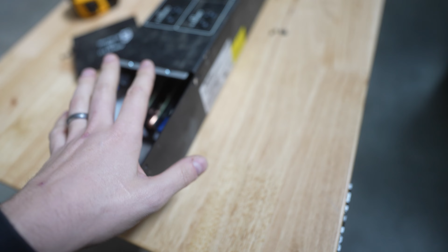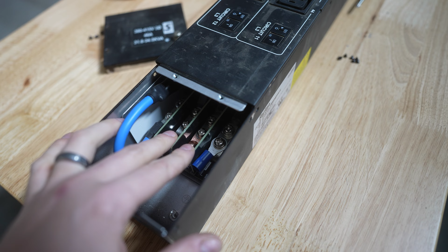Anyway, we're going to be using these PDUs. Why do we go with these ones? Because it's a 415 volt PDU, that's the transformer we have. We're not doing a 208 or 240 transformer, we're doing 415, meaning if you connect two legs together you get 415. Each leg is 240.